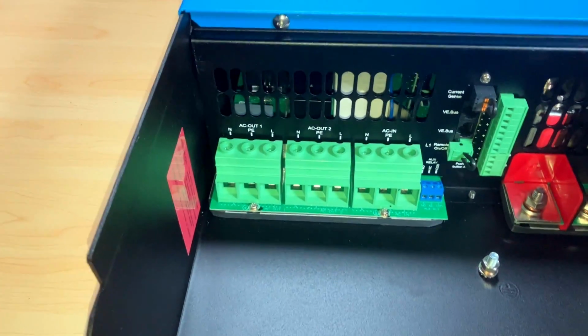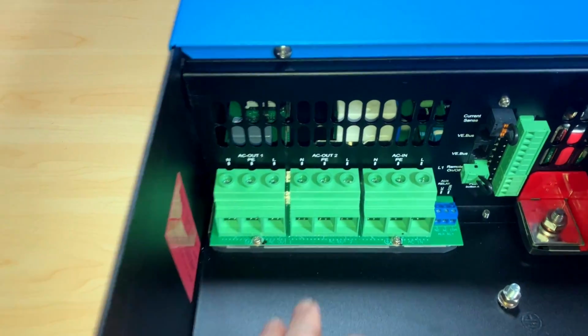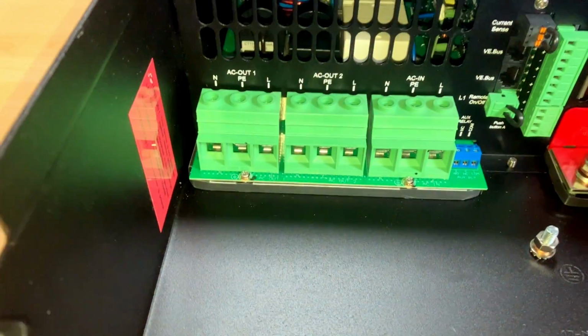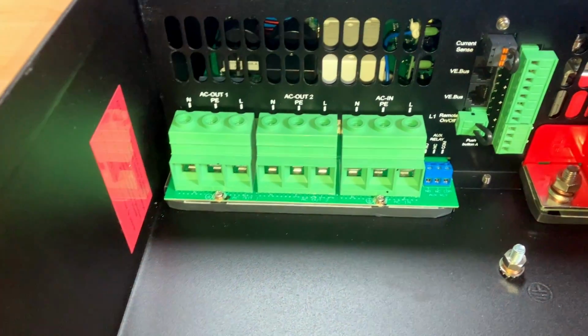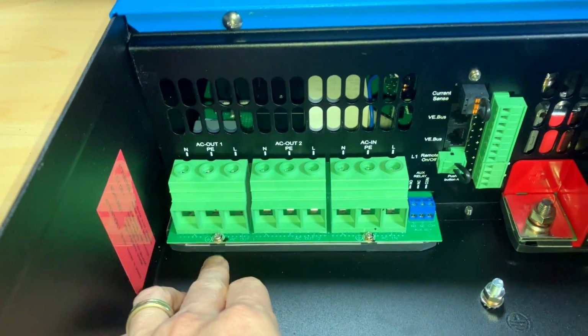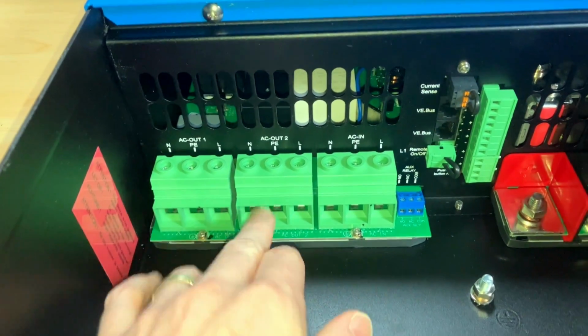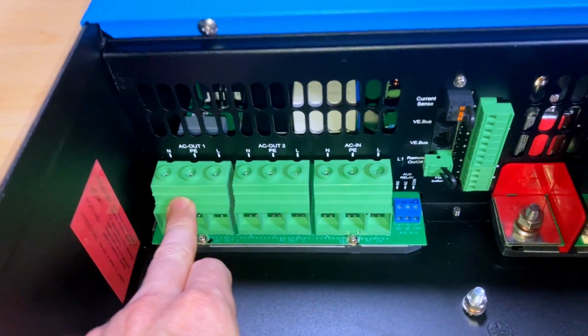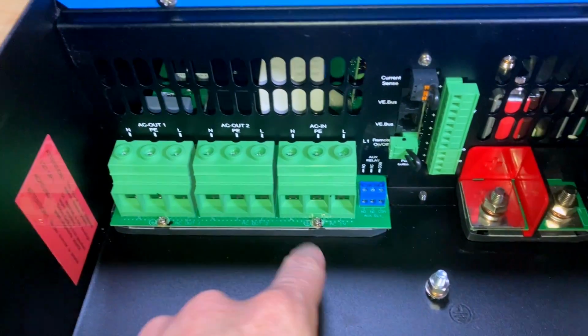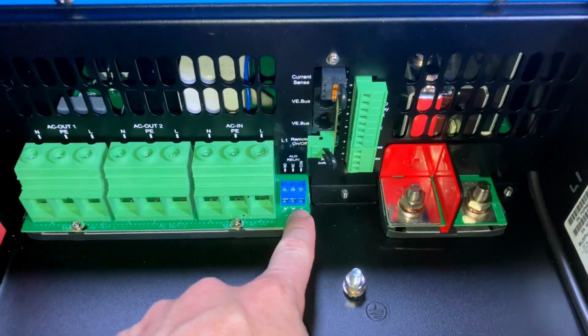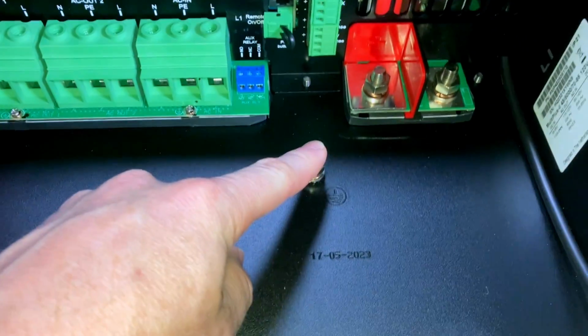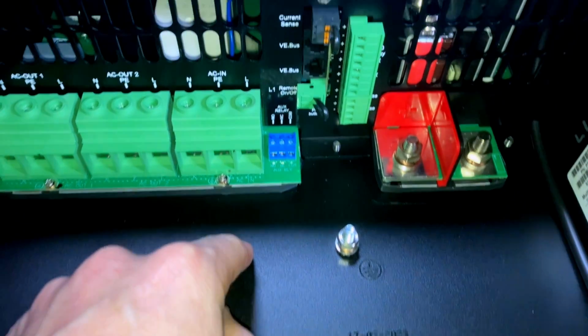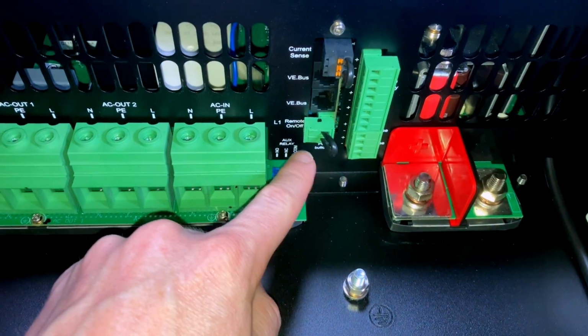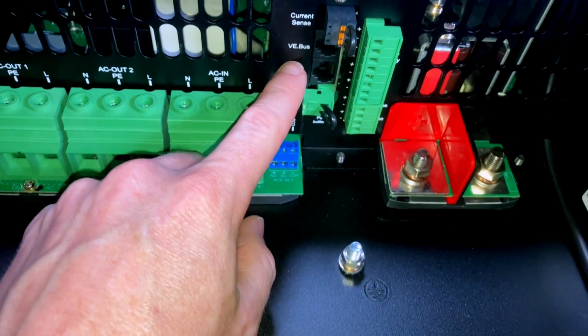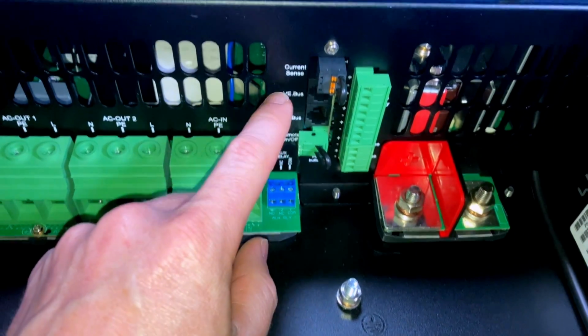Set that off to the side. So looking at the inside, they've got some beefy connections you can have down in here. I want to say these can handle up to 2 gauge wire now. But your AC out 1 and AC out 2, your AC in, you've got an auxiliary relay, a grounding stud, a remote on and off. You've got 2 connections for your VE bus, which we'll get into later.